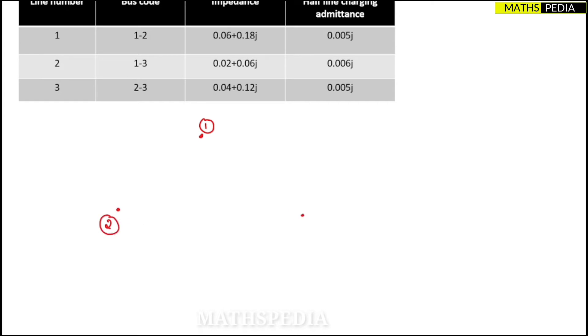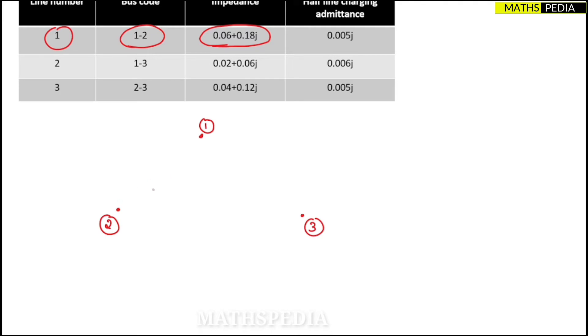Let me draw: node one, node two, and node three. Between node one and two, from the table, we have line number one with impedance 0.06 + j0.18. So we have one line between nodes one and two with that impedance.